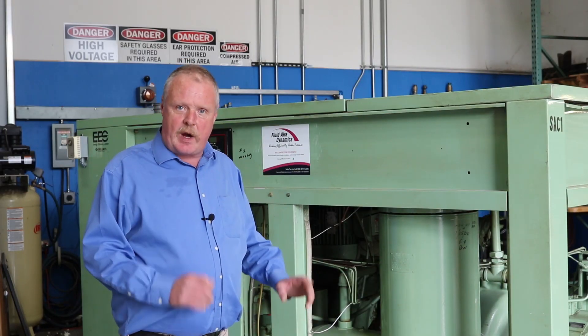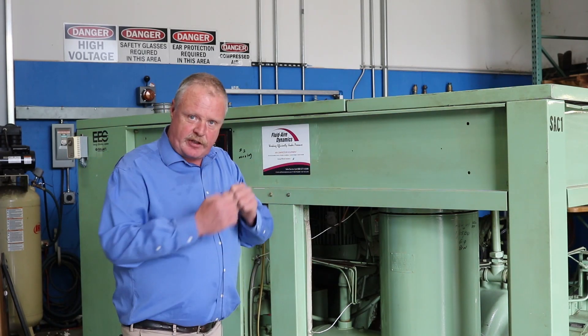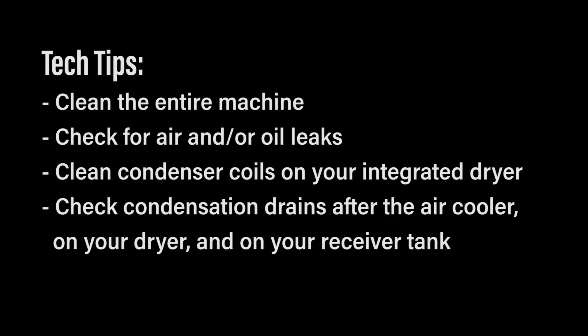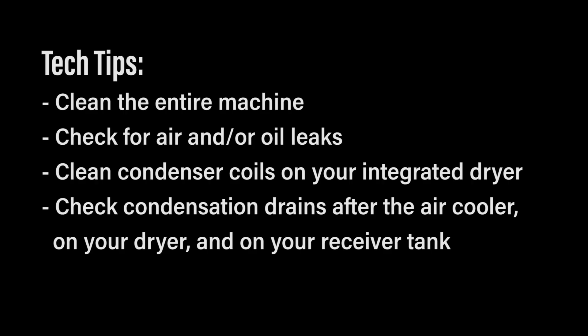Another item to check during the hot months is your condensation drains. Some compressors will have a condensation drain after the air cooler that discharges any condensation that collects. Be sure those traps are working properly, and also that the condensation drains on your dryer and your receiver tank are working properly. Some of these Wye strainers or condensation drains will have screens that need to be periodically cleaned — rust and particles can build up in a receiver over years and clog the screen, preventing condensation from being discharged. Be sure to visually inspect those as well.